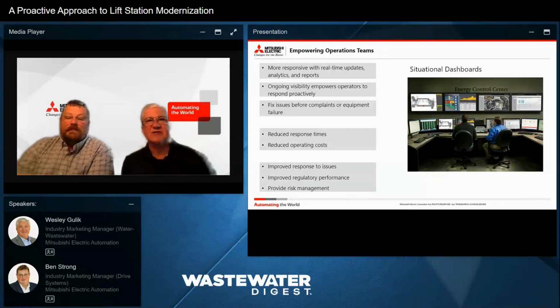So, empowering operations teams. We're noticing more and more users are implementing some sort of SCADA system. And we're just listing primary reasons why: more responsive with real-time updates, analytics, and reports. Because again, it's online, so you see firsthand what the issue is, and correct it firsthand, pretty much immediately. And ongoing visibility empowers operators to respond proactively, as opposed to physically going out there and hearing, hey, I hear this sound, it's probably at this pump or a temperature issue. Fix issues before complaints or equipment failure.